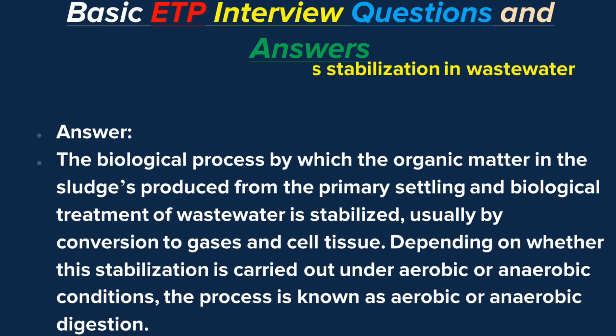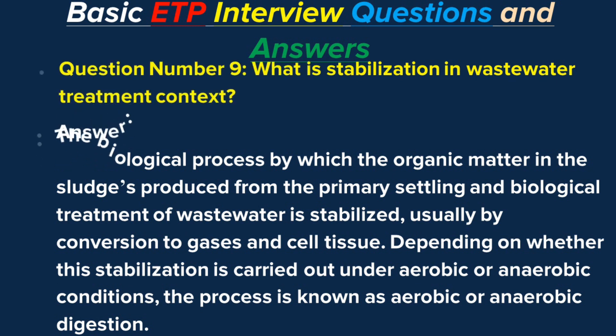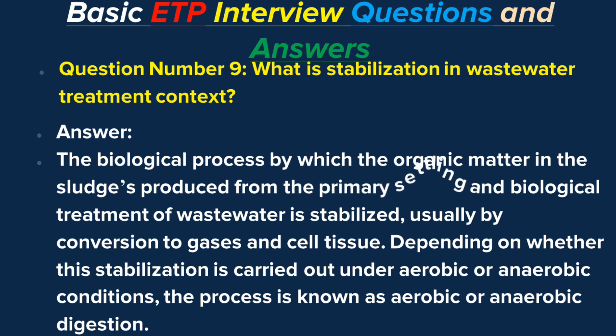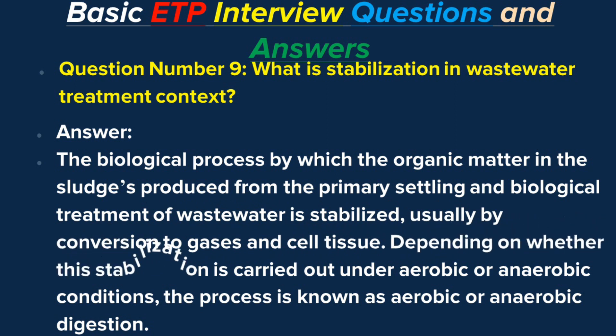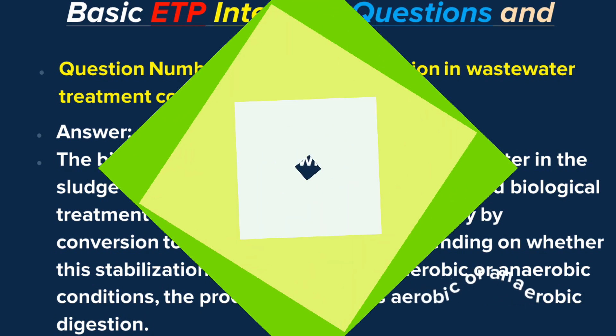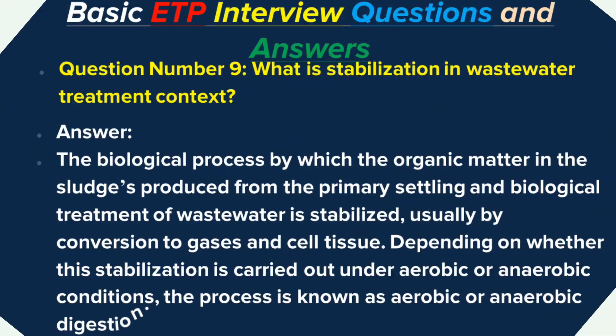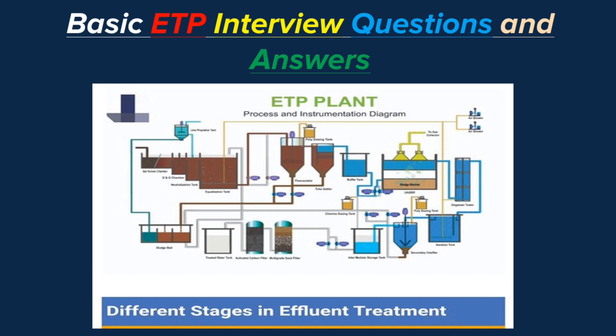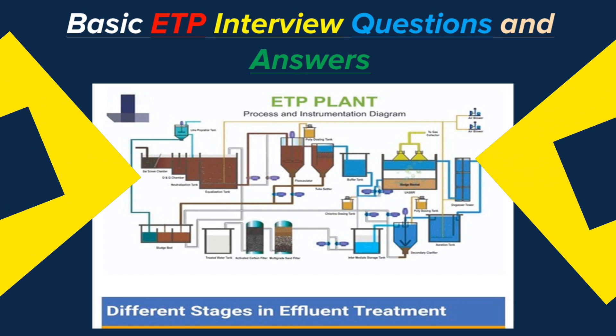Question number 9: What is stabilization in the wastewater treatment context? Answer. Stabilization is the biological process by which the organic matter in the sludge produced from primary settling and biological treatment of wastewater is stabilized, usually by conversion to gases and cell tissue. Depending on whether this stabilization is carried out under aerobic or anaerobic conditions, the process is known as aerobic or anaerobic digestion.